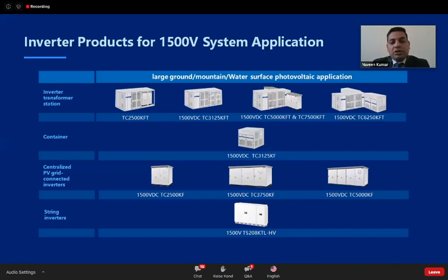Moving on to the container solution, we have a 1500 volt container solution with a capacity of 3.125 megawatt. For central inverters in 1500 volt technology, we have three ranges: 2.5 megawatt, 3.75 megawatt, and the biggest at 5 megawatt, one of the largest inverters available in the market. We also have string inverters, a 208 kilowatt, 1500 volt inverter, which can be used in utility scale projects.